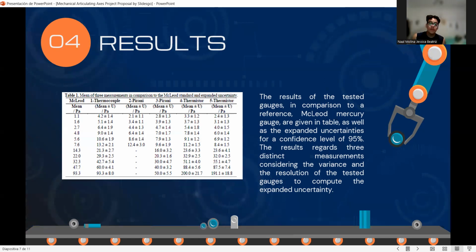The results of tested gauges in comparison to a reference, a McLeod mercury gauge, are given in the table. In this table, as well as the expanded uncertainties for a confidence level of 95%. The result regards three discrete measurements, considering the variance and the resolution of the test gauges to compute the expanded uncertainty.